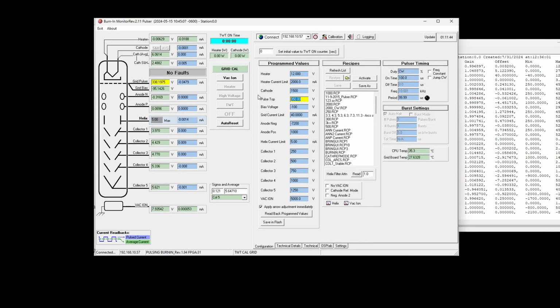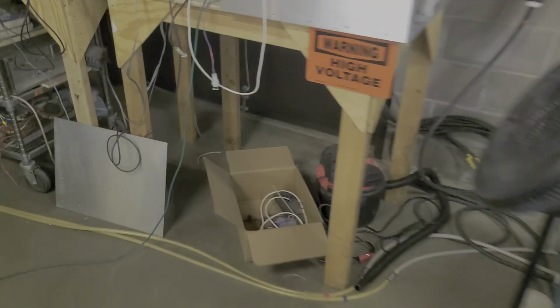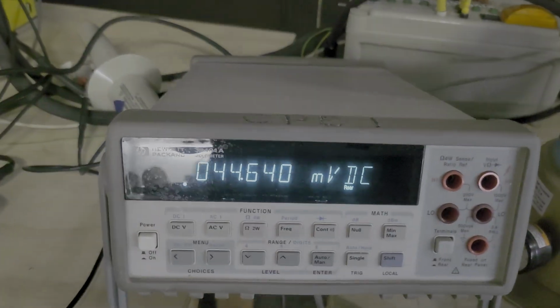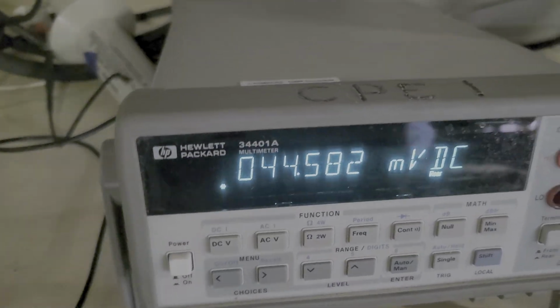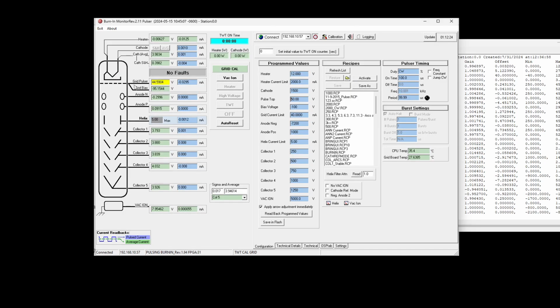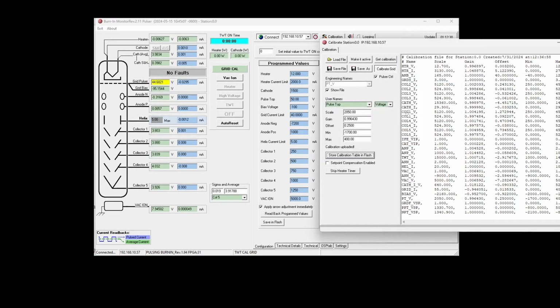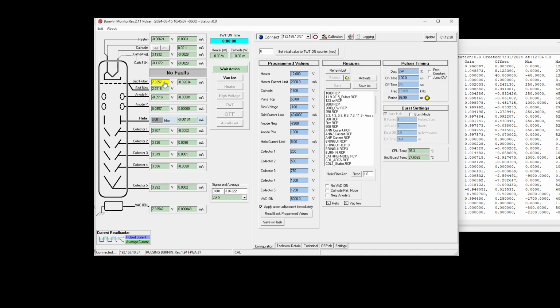Let's go one more iteration just to be consistent. 3 iterations of successive approximations. So at 50, 44.6, and that's exactly what we see: 44.6. I'm going to say this is good. So we're going to hit store calibration table in Flash and call it good. Now we can turn off our grid. Clear faults.